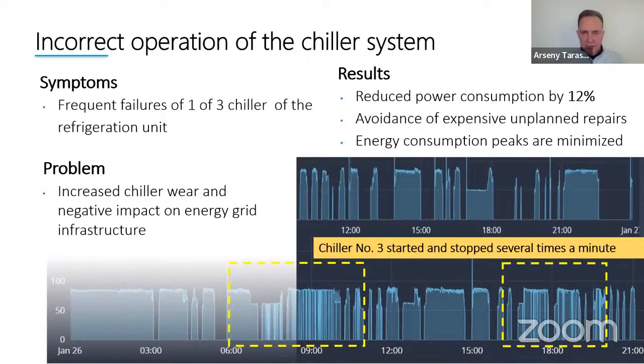When we analyzed the performance of those three chillers, which are really big to achieve minus 18 degrees in this warehouse, we realized the first and second chillers worked fine. You can see here what we call an electrocardiogram - no problem there. But chiller number 3 demonstrated really unusual and abnormal behavior in how it was operating. It's a typical issue, but they could not understand it without this detailed diagnostic tool.